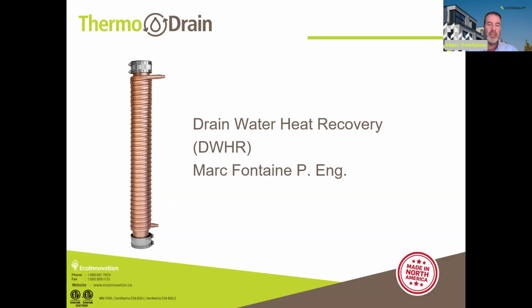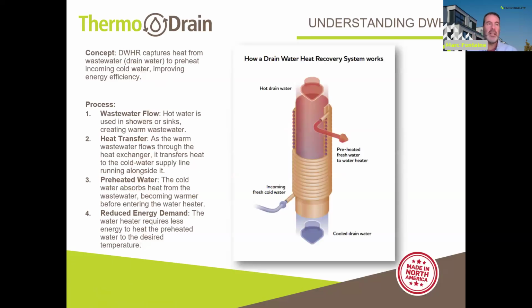So here you see the construction is essentially a central copper drain tube around which is wound a copper coil, which holds the potable water. And then on each end, you can see a no-hub mechanical coupling that's used to do the installation on the drain stack. We're going to go fairly quickly today on most slides. At the end, I'd like to have enough time for questions, and we can go back as required. So drain water heat recovery is essentially a device that's used to recover heat from waste heat, mainly coming from shower activities. And so the shower in the home is what uses the most hot water. Obviously, there's other sources of drain water that may be of interest, like a kitchen sink, for instance.